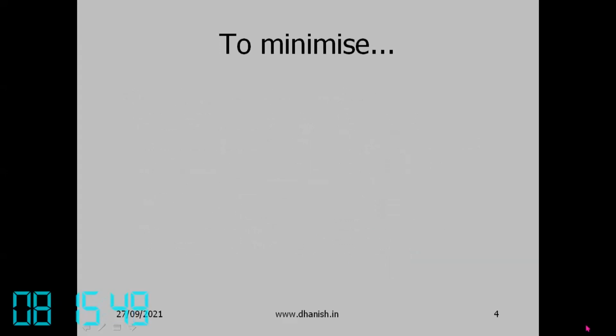So how can we minimize the errors due to the temperature change? So the very important practice is to avoid handling or minimize handling. Why? So what is your body temperature? Your body is 37 degrees Celsius. So if you touch an object, what will happen? The object will absorb heat and start expanding.